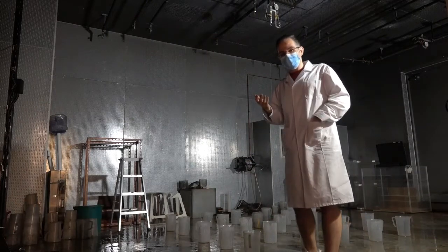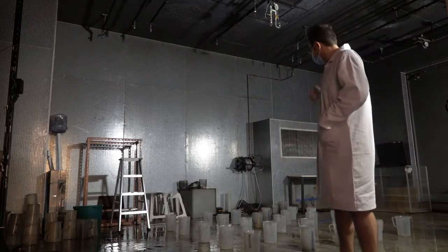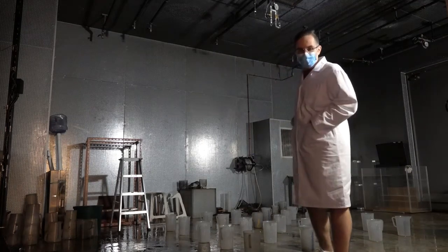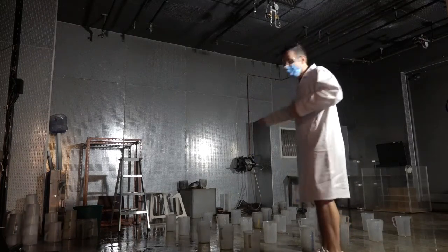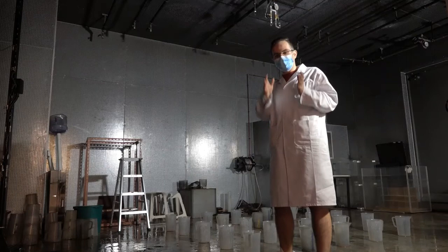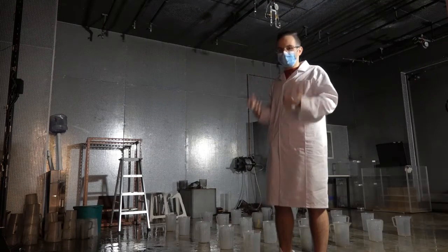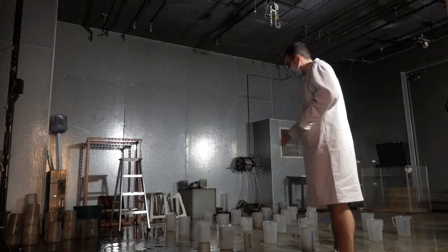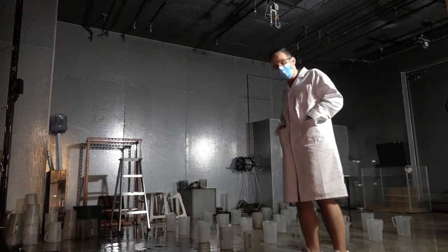What we will be doing now is we'll be testing how much water each sprinkler puts out, every different type, and we'll see how this water is distributed. You saw the pattern that comes out of the sprinkler. Now we want to see where this water falls in an area around the sprinkler, under the sprinkler. This will help us understand how we can distribute the sprinklers in compartments or buildings so we can effectively suppress fires. We distributed these collection spots about half a meter apart each, and we'll give you all the data that we get from this experiment.